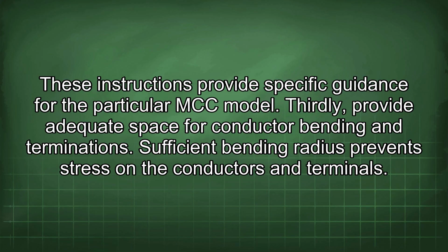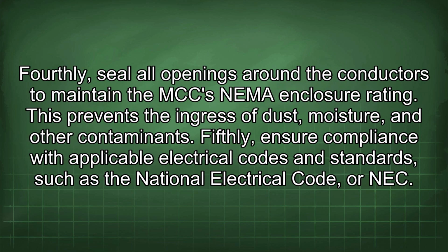Thirdly, provide adequate space for conductor bending and terminations. Sufficient bending radius prevents stress on the conductors and terminals. Fourthly, seal all openings around the conductors to maintain the MCC NEMA enclosure rating. This prevents the ingress of dust, moisture, and other contaminants.